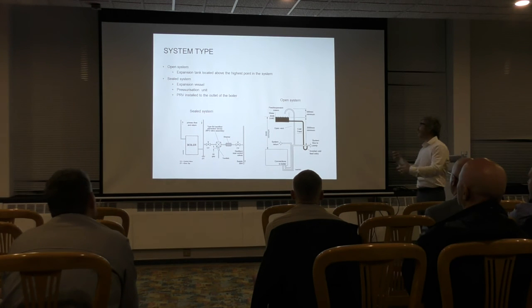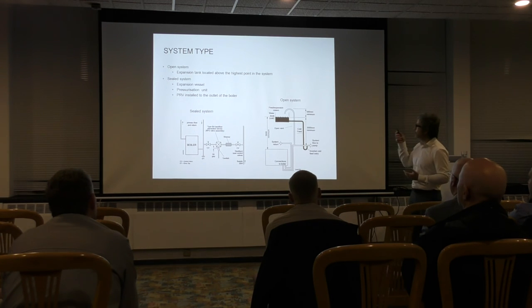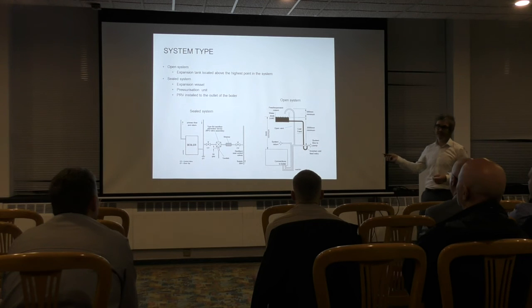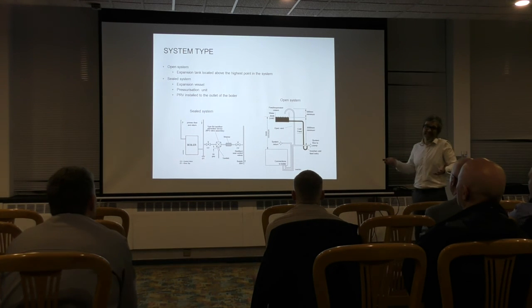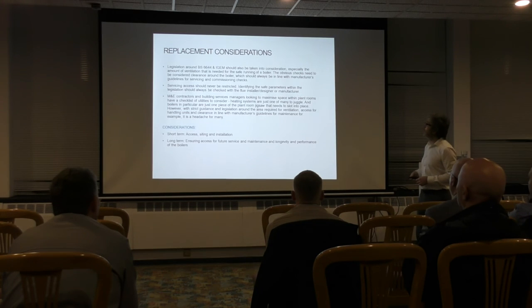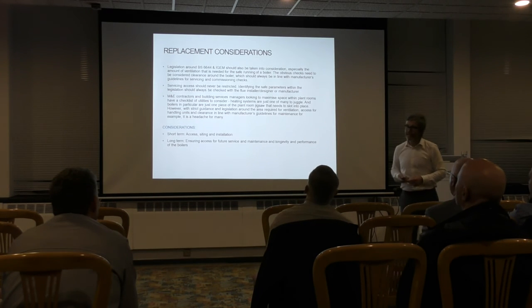Obviously, system type, again, we've kind of gone over this earlier about sealed system, open venting system. There's just some diagrams there on which is which. As I said, open venting, pretty old school. You really want to switch over to a sealed system. But as I said earlier, if it is an open venting system, you can keep it. It just really narrows down your boiler selection. And then really, I suppose, replacement considerations.